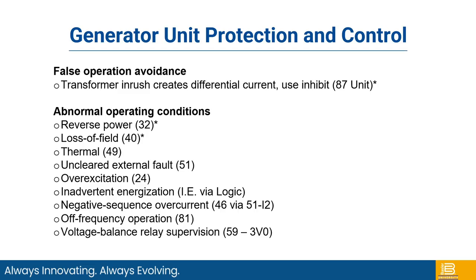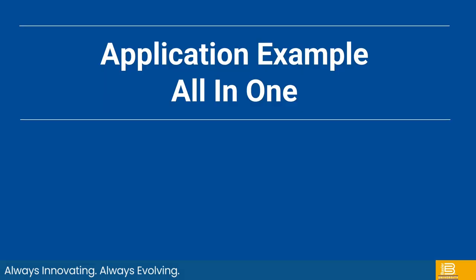We have logic templates that you can get from our product page on the BE1-FLEX product page. Negative sequence overcurrent protection with negative sequence via 51 or the 50 element. Off frequency operation and voltage balance supervision with the 59 element and 3V0 using that mode in the 59 element.